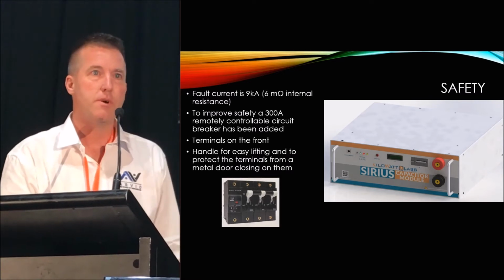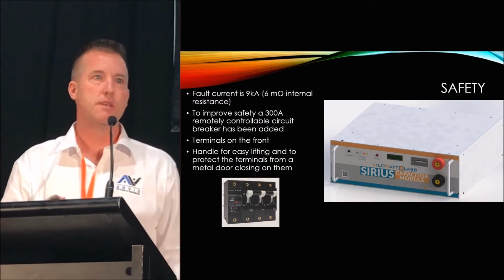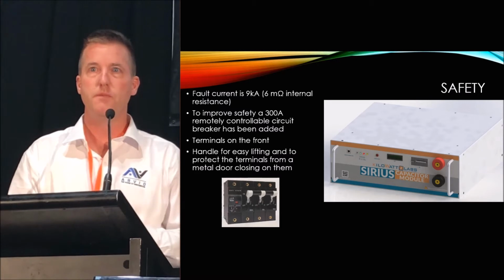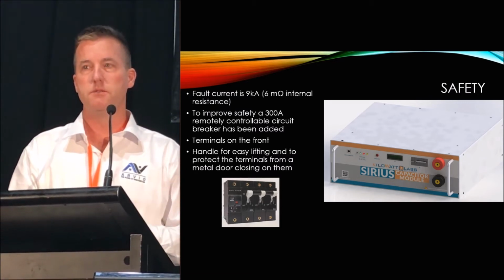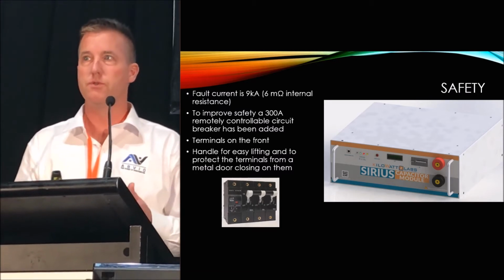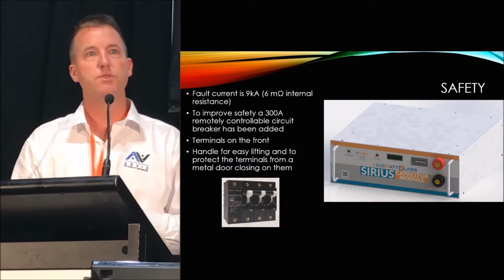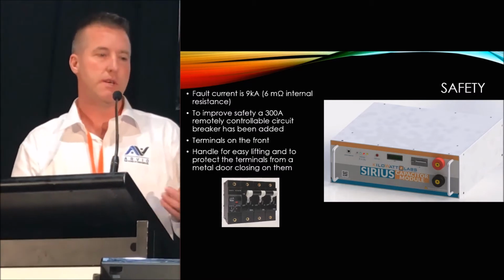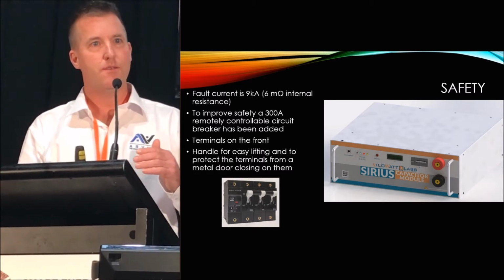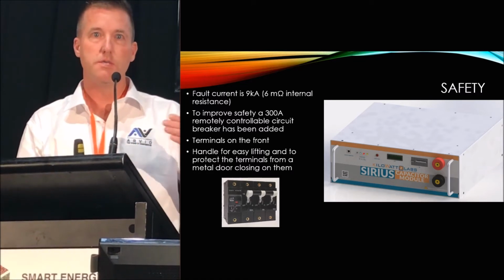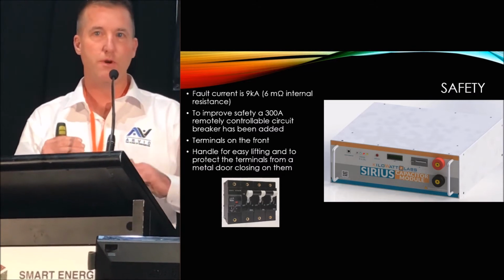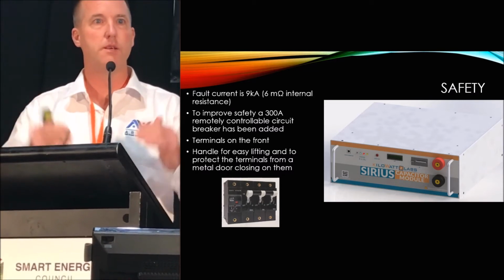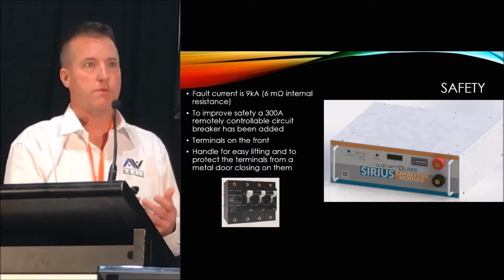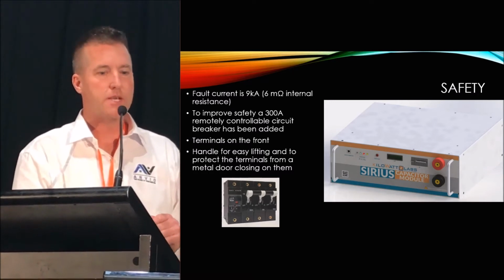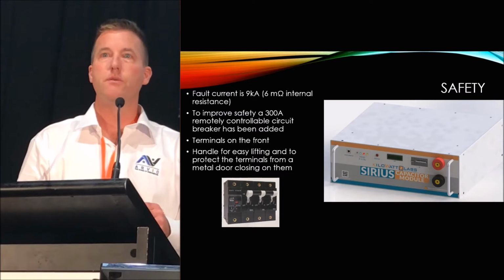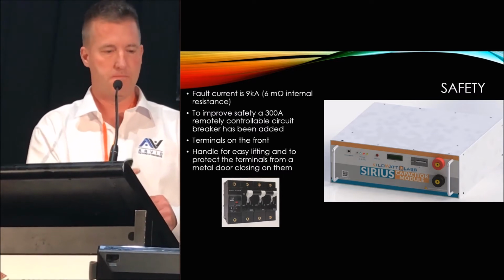It also helps us commission it remotely and bring the capacitors up to the same voltage before we parallel them. If you had, say, 10 capacitor banks in parallel and wanted to commission the system, they should all be about the same voltage first. Using our software, we can turn on the lowest bank and charge it until it matches the highest bank voltage, then turn that one off and turn the next one on, automatically commissioning the system without worrying about user error. If you accidentally tried to parallel them at different voltages, the circuit breaker would trip.